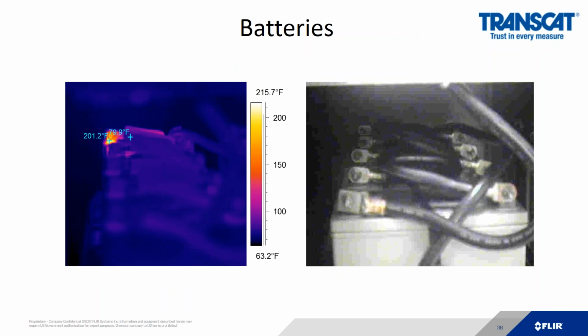If you use batteries, an uninterruptible power source, here we see a 120-degree temp rise on a battery that is not giving off any power or supplying load to the facility. This is under very light load. If there was an outage and this battery power supply had to kick on, there's a good chance that this would explode, because once load was placed on the system, that 120-degree rise would skyrocket exponentially.